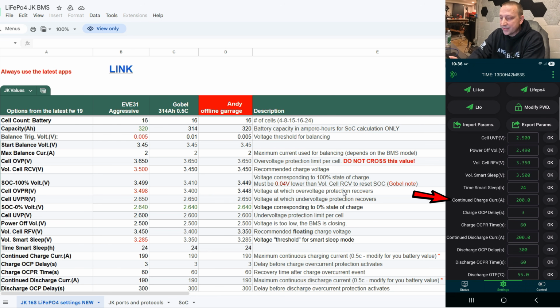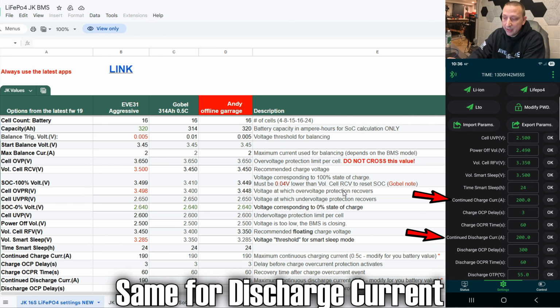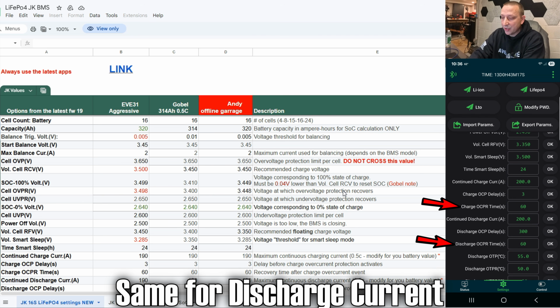Next below that is your continued charge current, already set for 200, which I left since it's a 200 amp BMS inside. Below that is the charge over current protection delay - if you hit 200 amps for 3 seconds, it'll shut off. Then there's a charge over current protection recovery time - it'll wait 60 seconds and try again, and if it still senses you're over 200 amps, it'll restart that cycle.